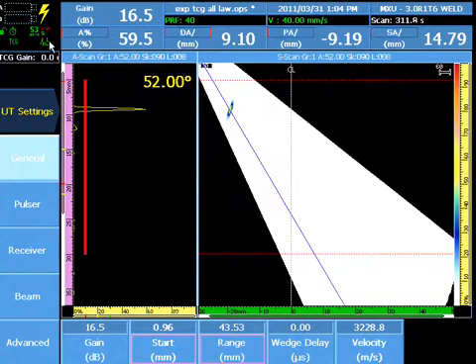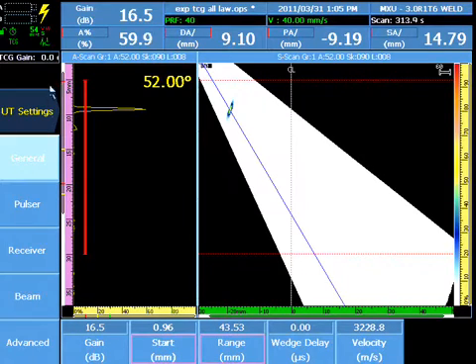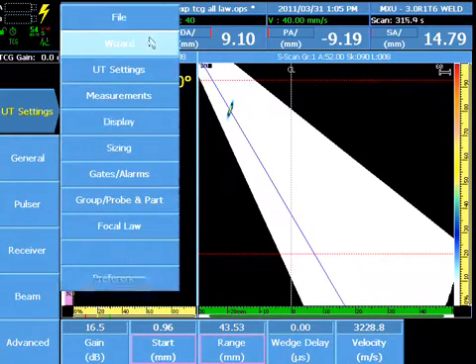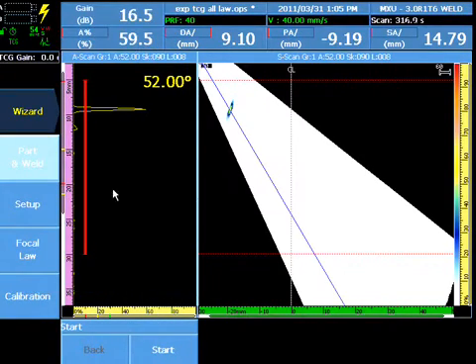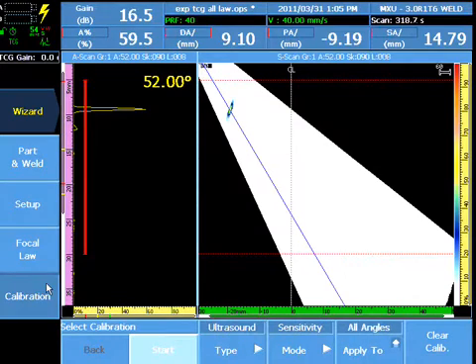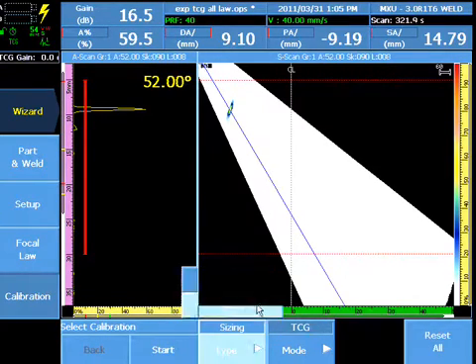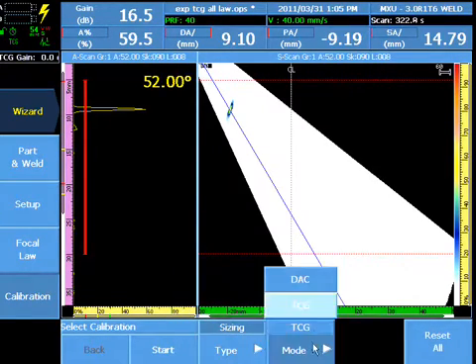To calibrate for TCG, select Menu, Wizard, Calibration, Type, Sizing, Mode, TCG.